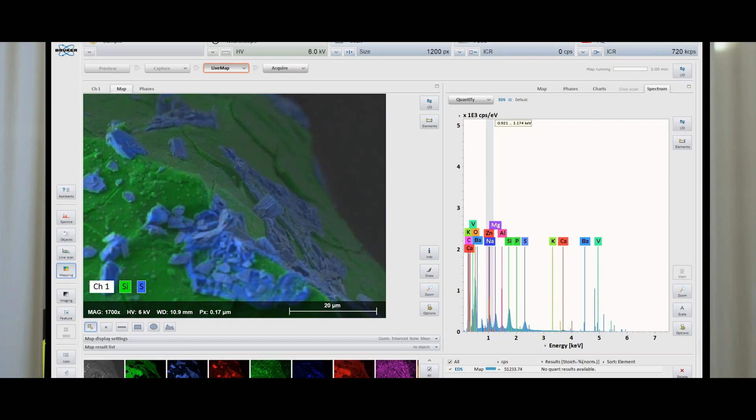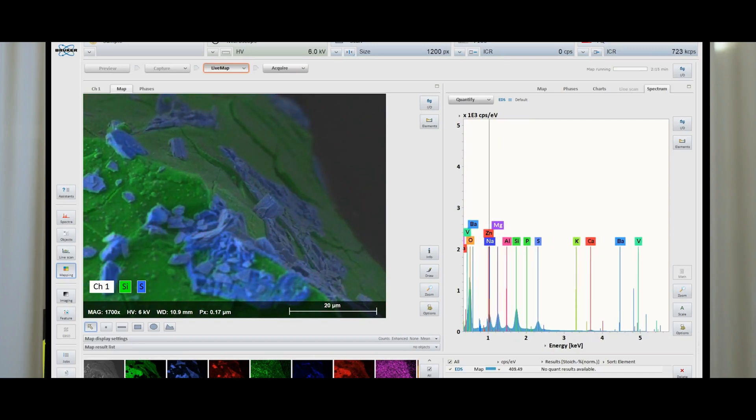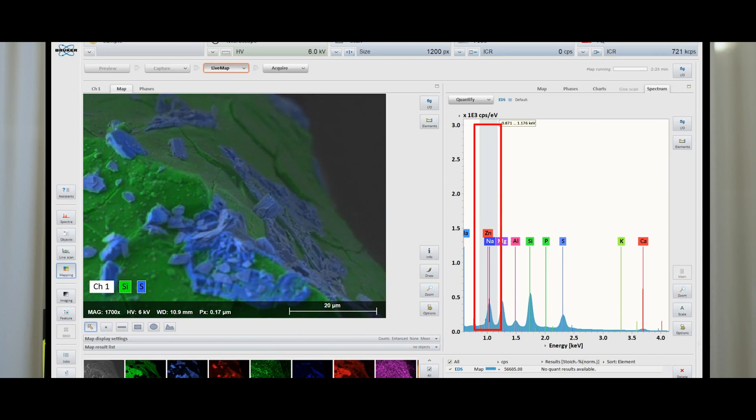It also reduces shadowing effects — the effect of topography is not so pronounced — and you can really deconvolve the peaks with the ESPRIT deconvolution techniques. When you combine the Flat Quad with something like live mapping, which is a software upgrade, you really turn your microscope into a real-time chemical or EDS imaging detector. You can move around your sample, quickly find your regions or areas of interest, and then take real quantifiable data in one step with one detector. It's really changed the way that I look at and do my EDS analysis of my samples.